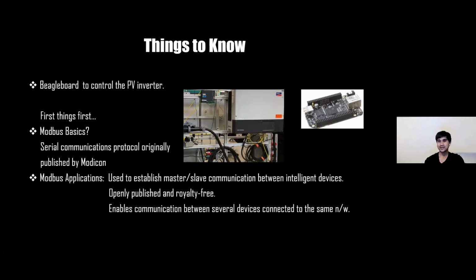Now, unlike TCP/IP and UDP, Modbus is a communication protocol, as I explained in the earlier slide. It's extensively used in SCADA systems, and it was also used in our case. The Modbus serial protocol is a master-slave protocol. One master controls Modbus data transactions with multiple slaves that respond to the master's requests to read from or write data to the slaves. There are various read and write operations that can be performed within the Modbus topology.